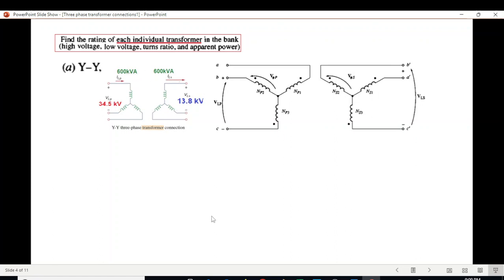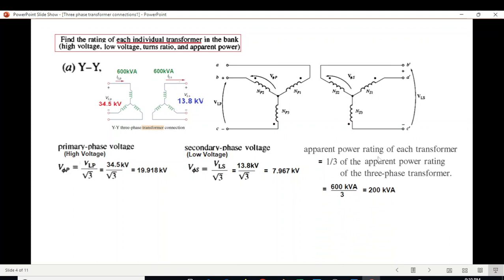Primary voltage, primary line voltage, secondary line voltage, and apparent power 600 kVA - power remains the same on primary and secondary side. We need to find the high voltage of the primary side. In Y connection, line voltage and phase voltage have a relation - the phase voltage is V_line divided by √3. So 34.5 divided by √3 equals 19.918. On the secondary side, also Y-Y, using the same formula we get secondary phase voltage of 7.967.